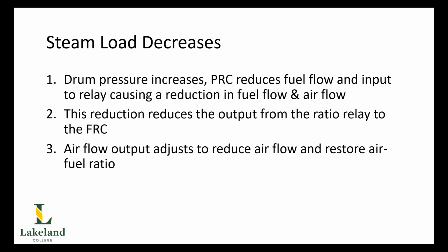So now a new set point is generated to go into the airflow recording controller, and that is going to generate another output through to the modulating relay and down to the air damper drive to reduce the airflow, which is going to restore our air to fuel ratio for the new firing rate. So that's how this one responds.